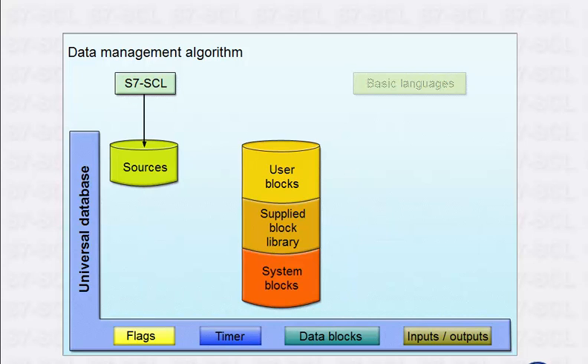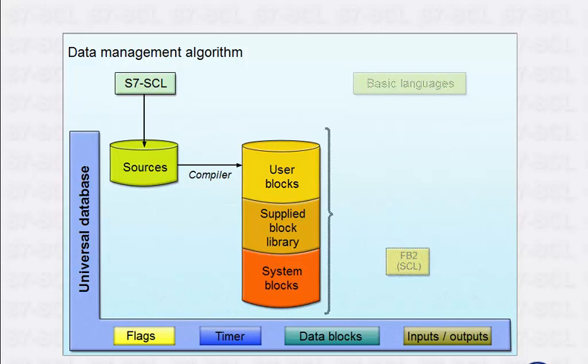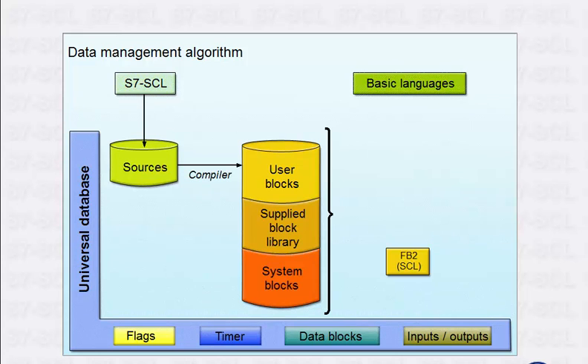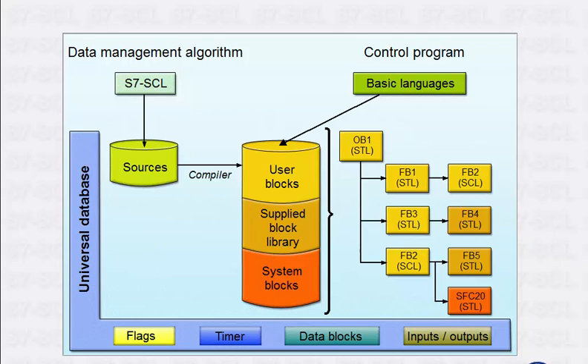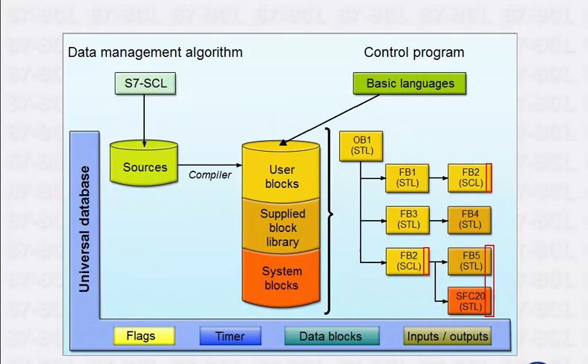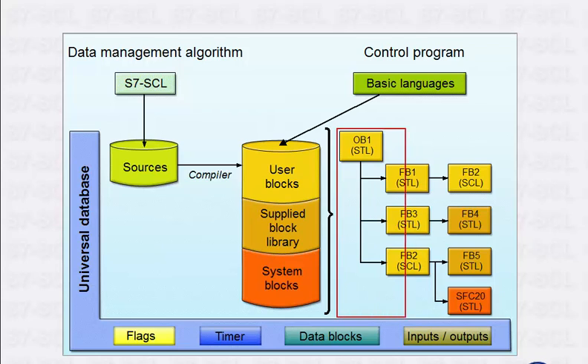Once the algorithm has been implemented in one or more S7-SCL sources, the built-in S7-SCL compiler now generates one or more STEP 7 blocks. In this way, a control program written in one of the basic languages can implement a call hierarchy. The algorithm implemented in FB2 can thus be used repeatedly and its behavior influenced by transferring the relevant parameters. By combining blocks that fulfill specific functions in a precise way, you can greatly reduce the development time.